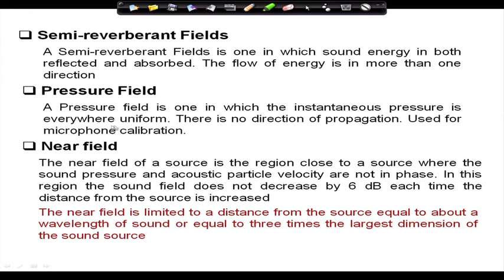Okay. Now, there is another sound field called the pressure field. A pressure field is one in which the instantaneous pressure is uniform everywhere. If the instantaneous sound pressure is the same everywhere, then we call it a pressure sound field. This is used for microphone calibration. For microphone calibration, we use this kind of uniform pressure sound field.